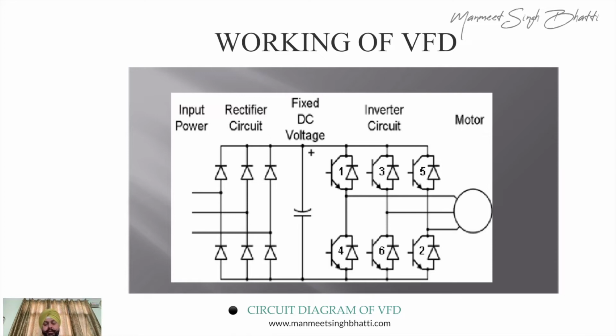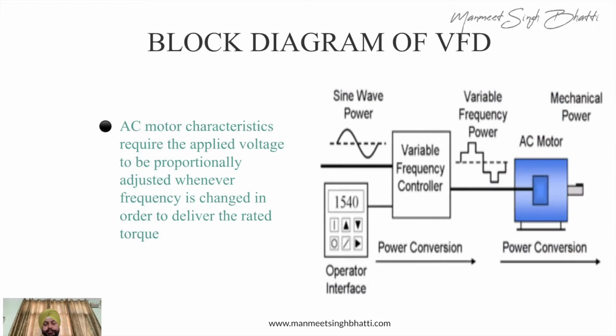So whatever the disturbance is in the DC circuit because of the AC input, automatically it gets smoothened, and the same DC is fed to your inverter circuit. So if you see, we have the inverter circuit at the end. This inverter circuit converts that DC power to AC power, which is fed directly to the motor. So if you see, this is the waveform characteristic. This is more explanatory to you how it is going to work and how the motor actually gets affected.